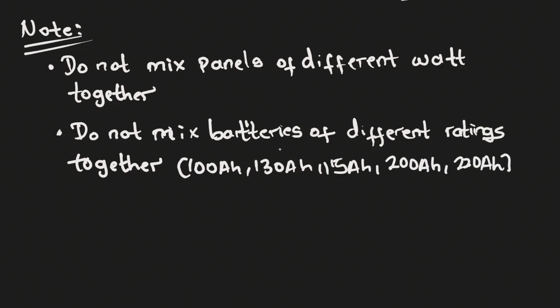Your lithium ion batteries are rated in kilowatt hour. You can have 5 kilowatt hour, 10 kilowatt hour, or 15 kilowatt hour. If you have a 100 Ah battery and a 200 Ah battery, do not mix them together. It's not advisable. Same thing for the lithium ion battery. If you have a 10 kilowatt hour and a 5 kilowatt hour, do not mix them together.